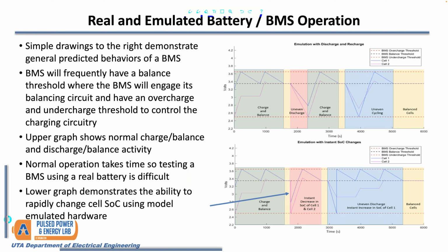So how would a BMS operate? I talked about how it would balance the cells. How does it do that? The first, predictive way many BMSs operate is by using manually set thresholds. On the balance cards shown earlier, there's a balance threshold denoted by the dotted black line, which is the point at which the BMS closes its contact and dissipates excess power on the cell. Then there are red lines where the BMS will open up or even request a charge or load to dissipate power or get power into the battery, denoted by the two dotted red lines. Looking at the top graph, the BMS will open up at the dotted red line and dissipate until it reaches the balance threshold, then recharge and continue this process until the cells are in balance at that threshold line.